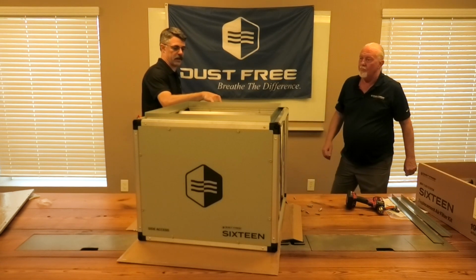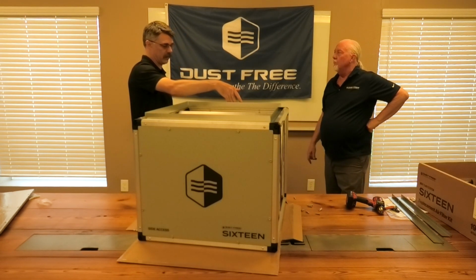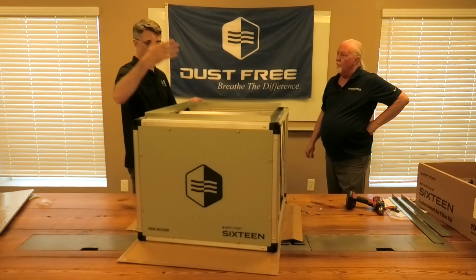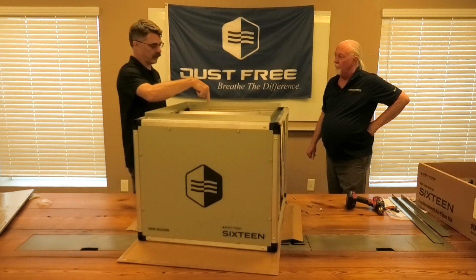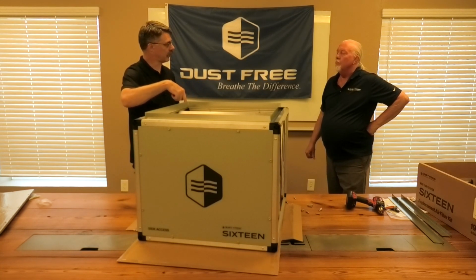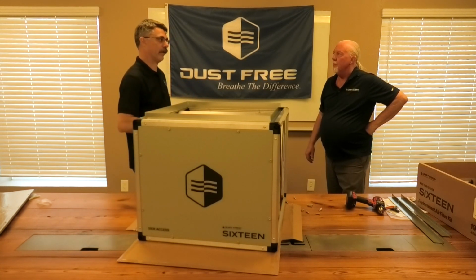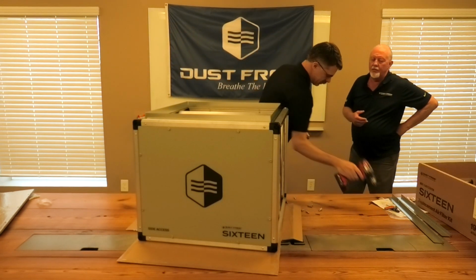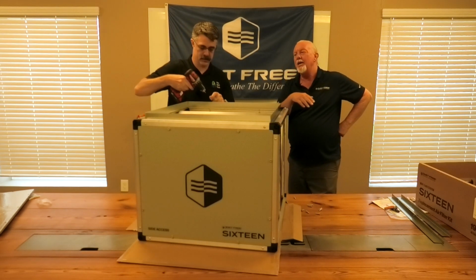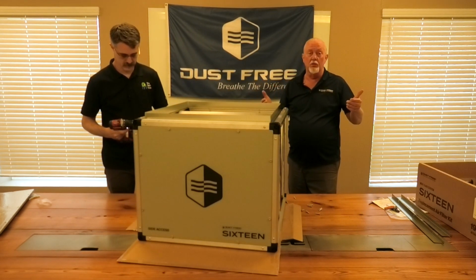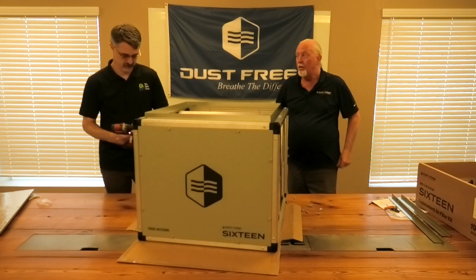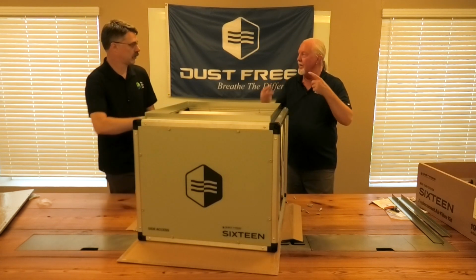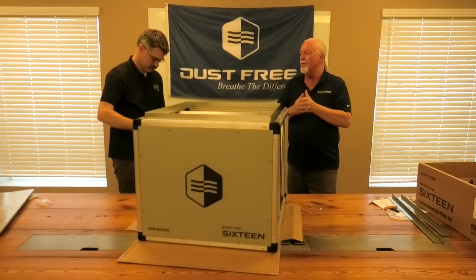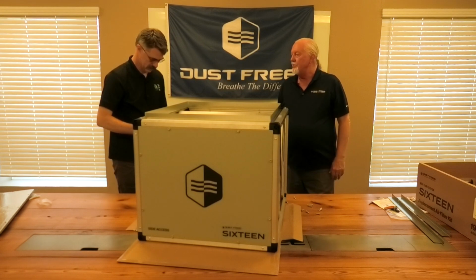I'd say this gap too, if you had that half inch flange on the end of your duct dropping down over this, that's a great place to stick some caulk. Absolutely, and boy, that's going to be beautifully tight. Actually, for those of you that do sheet metal, a flange over flange is considered a correct mechanical attachment when you're talking about sheet metal, other than a Pittsburgh lock or an S and drive or whatever, but flange over flange is just a solid way to do a connection.